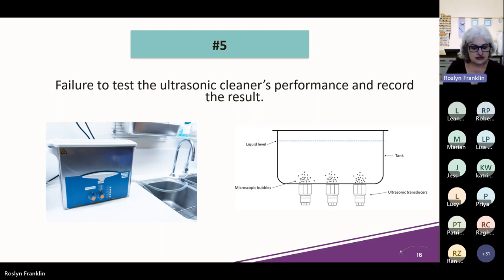So like a Helix or a Bowie-Dick test, which is a visual check, once again we do a test where we visually look. An ultrasonic cleaner works by sending sound waves through the water, which then cleans or scrubs the instrument by way of lots of microscopic vacuum bubbles. These bubbles are created by transducers.